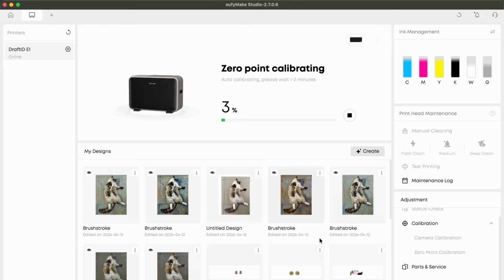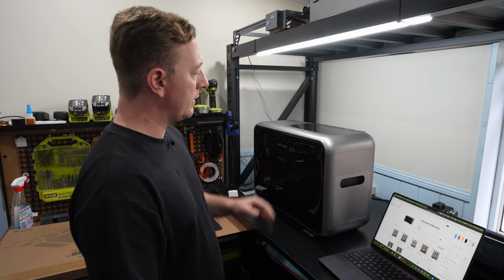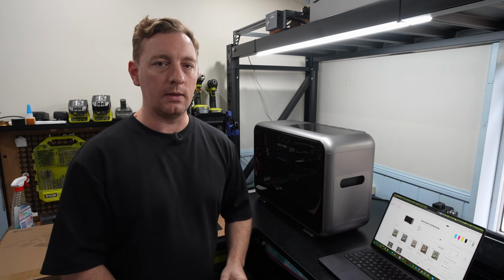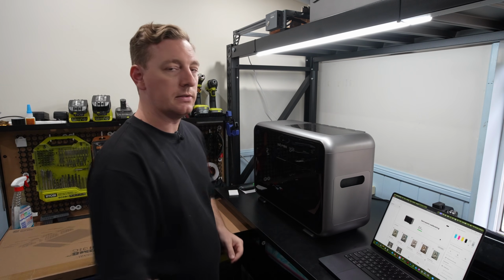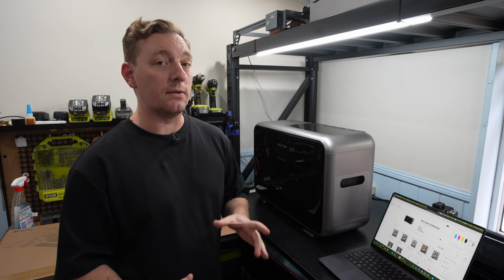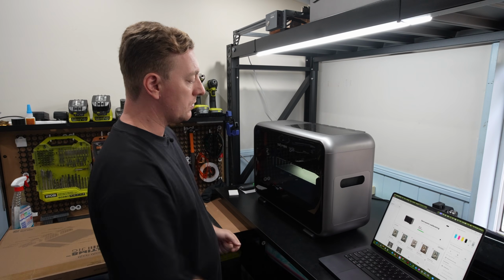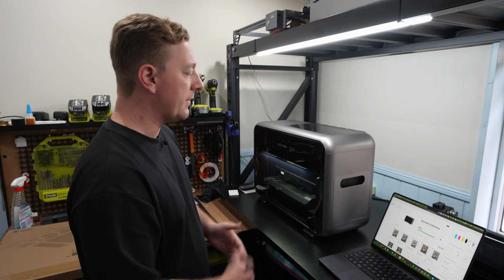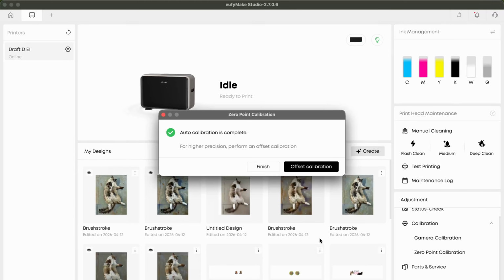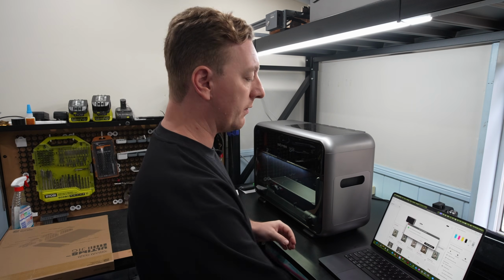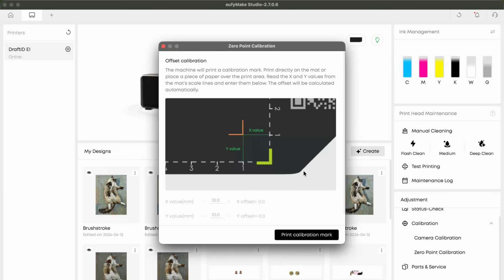And it says this should take about 1 to 2 minutes to do. I believe what it's doing is it is using the camera on board to find that 00 point. It's trying to do its own compensation to make sure it can find and align that correctly. That is done now, and it is asking us if we want to go into the next stage for the offset calibration for even higher precision. So why not? Let's try and make this the best we can. So we click on offset calibration.